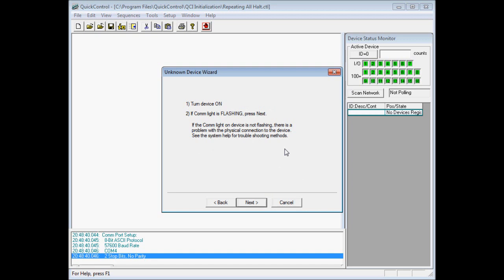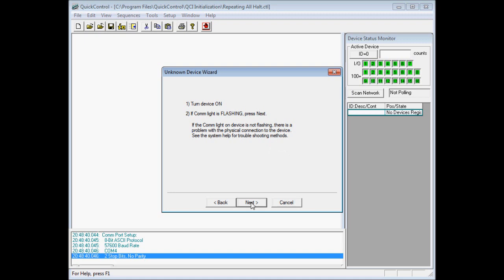As we power on, the red communication LED on the controller should be flashing at a fast rate. If it's not flashing, check that you selected the correct communication port and double check your communication wiring. If the red COM LED is flashing, go ahead and click next.